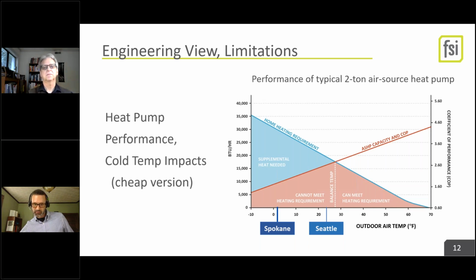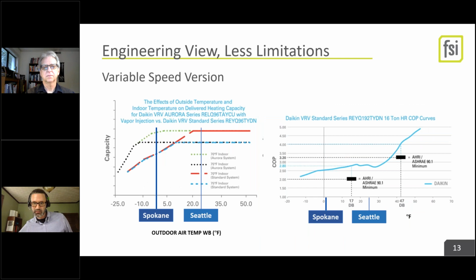For variable speed compressors or inverter driven compressors, that's not true anymore. If you look at the chart on the right, this is from Daikin, and it's just their VRF based system. You can see in Spokane, you've got to get the slightly extended temperature version, but it will retain near full capacity, well below what we would expect in Spokane. Seattle, you can get anything, and it's going to have full heating capacity without electric resistance backup. And this occurs also for inverter-driven compressors. Importantly, you can see the COP drops in heating mode, but in Spokane it only drops to 2.5. So you're still getting 2.5 times more heat than the work you put in. I would take that any day over electric resistance.